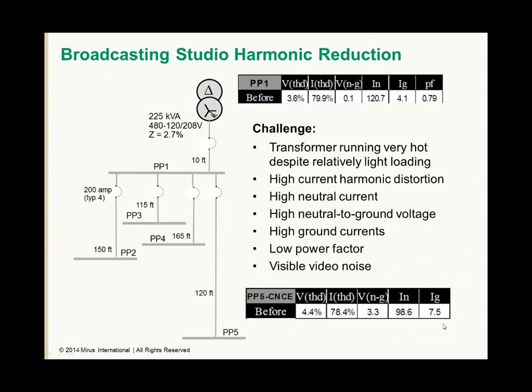So here we can see the ground current at one of the power panels, power panel 5: 7.5 amps ground current, almost 100 amps of neutral current at this panel, very high current distortion, high neutral to ground voltages. Up at the transformer, you can see the neutral current coming from all the panels into the transformer, 120 amps. Ground currents 4.1, a little less than it was at the panel, but still much higher than they wanted. Very low power factor due to the harmonic content.